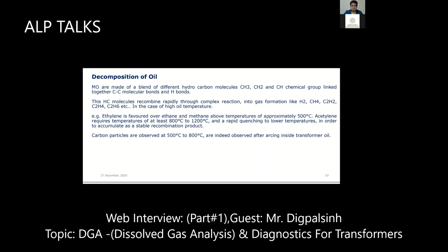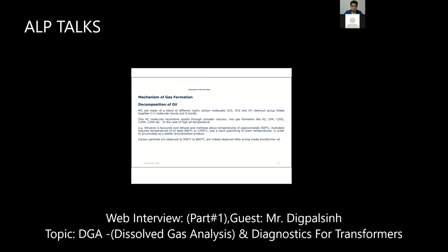This happens in the cases of arcing. In the OLTC tank, you will always find this, because when OLTC taps are changed, some arc is produced inside. So, in short, at high temperature, you will also see CO and CO2 with ethylene, in the case of decomposition of oil.